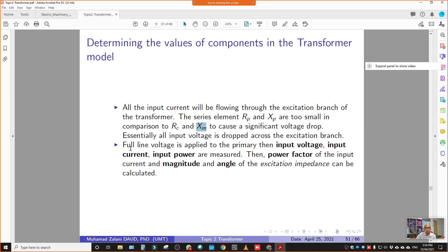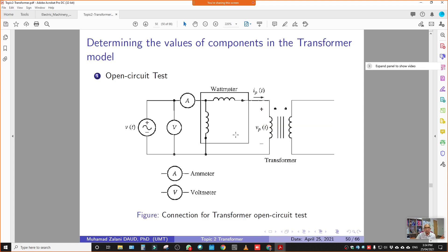Once the full-line voltage is applied to the transformer primary side, we record the measurements from the meters: VOC — the open circuit voltage in volts, IOC — the open circuit current in amperes, and POC — the open circuit power in watts. So we have three values: POC, IOC, and VOC.